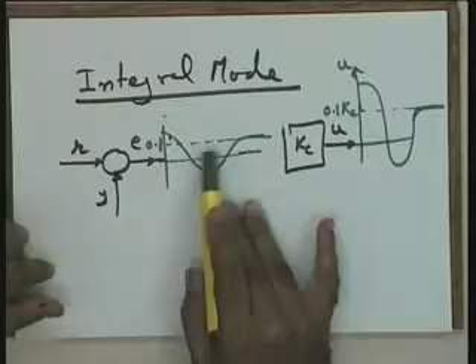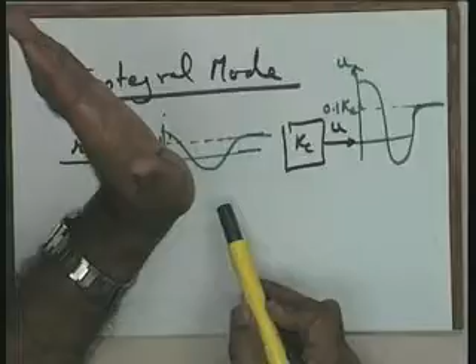So, it means your original equilibrium was obtained by adjusting the electropneumatic transducer. Now, the new equilibrium has come. The new equilibrium now requires a different amount of energy, and you are not going back to the original system to retune the electropneumatic transducer to get the new equilibrium value of the heat. I hope you are getting my point. So, how will the new equilibrium come? The new equilibrium can come only from additional energy coming, and that additional energy will come only if the error signal is present. So, it means the error signal is a must. If the error signal is equal to 0, it means you have come back to the original equilibrium position, which you are not able to, because the system is driven to the new situation.